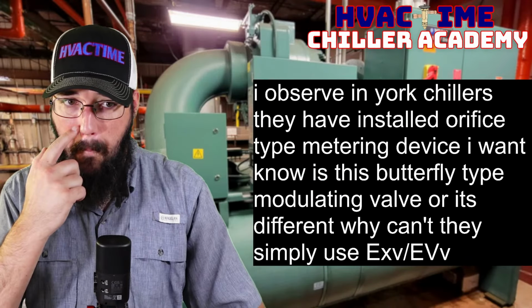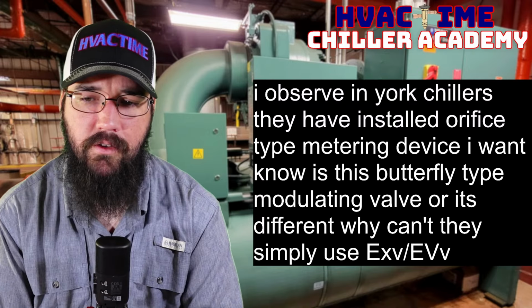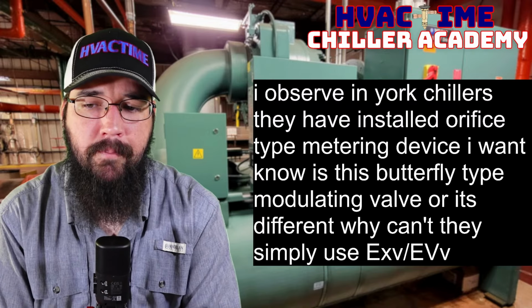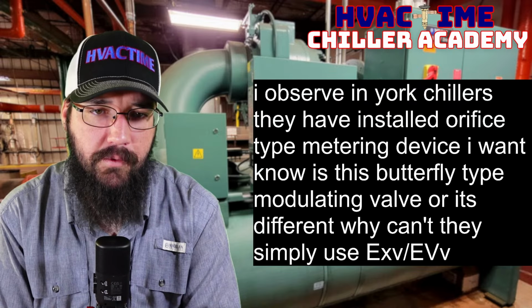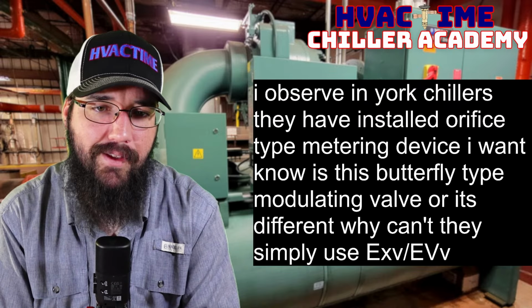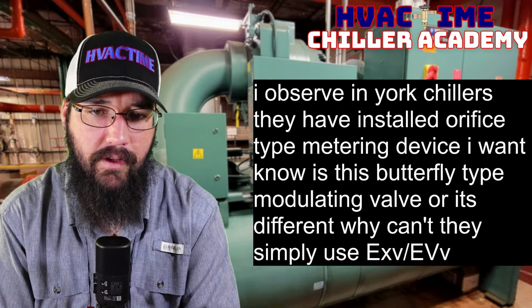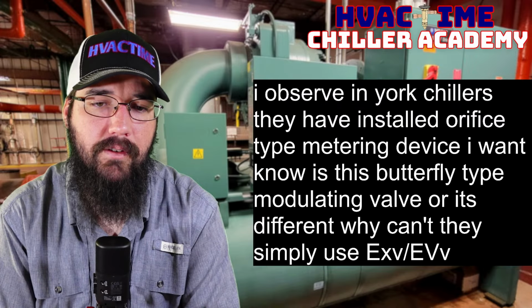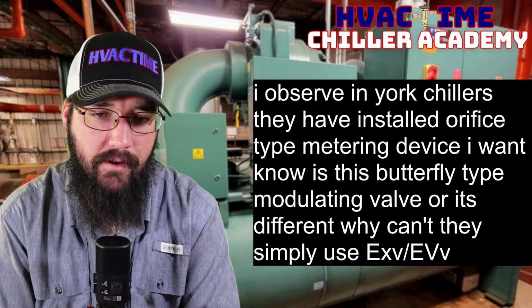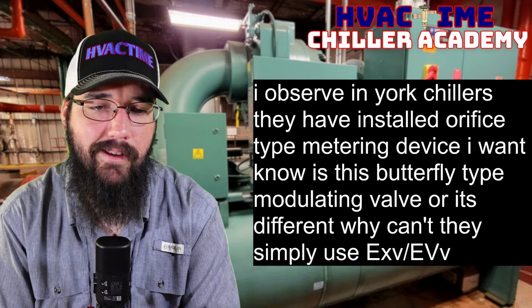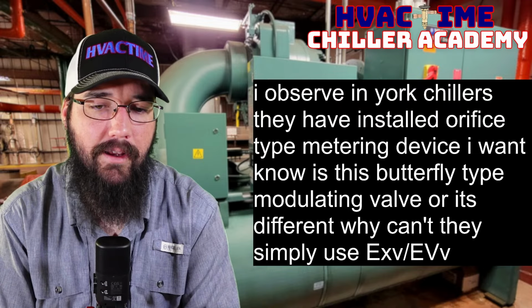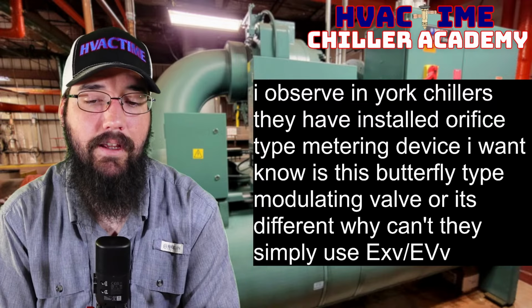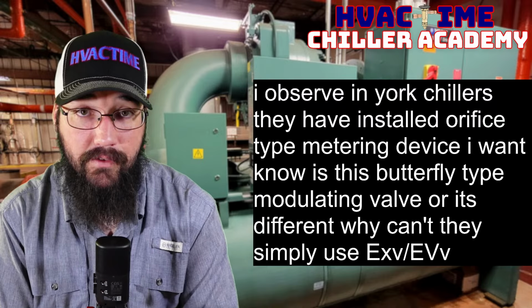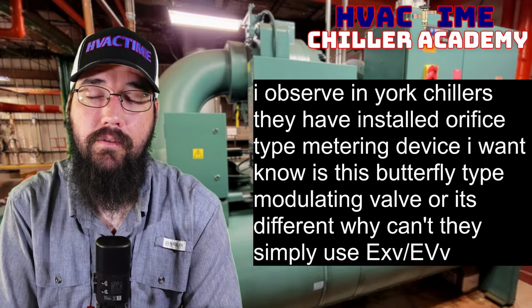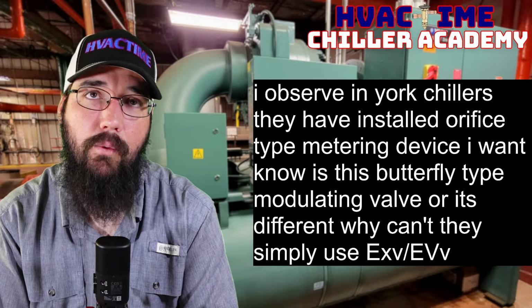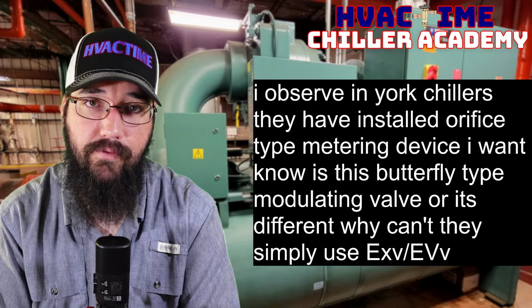All right, just so we're all on the same page: I observe in York chillers they have installed orifice type metering devices. I want to know, is this a butterfly type modulating valve, or is it different? Why can't they simply use an EXV? It is a butterfly type of valve, in short. Now we call it a variable orifice valve.